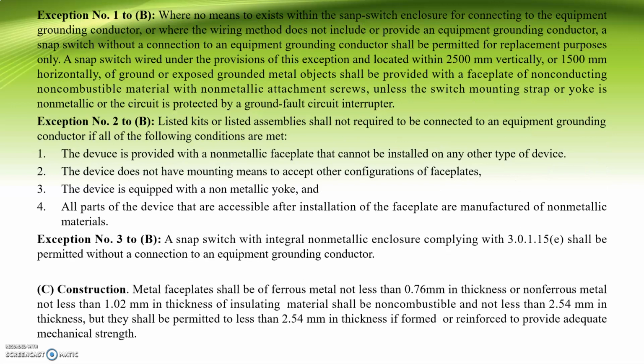Exception number 1 to B. So where no means exists within the snap switch enclosure for connecting to the equipment grounding conductor, or where the wiring method does not include or provide an equipment grounding conductor, a snap switch without a connection to an equipment grounding conductor shall be permitted for replacement purposes only.